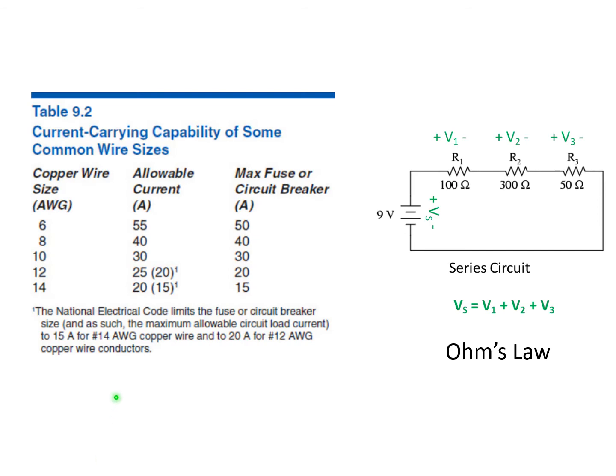And taking a look at current carrying capacity of different size wire. Wire is, at least in the U.S., specified by AWG, or American Wire Gauge sizes. And in a gauging system like this, the smaller the number, the larger the wire. So what we end up with is, say at 14 gauge, 14 AWG, has an allowable current of 20 amps, but the breaker, according to the National Electrical Code, needs to be set at 15 amps. So that way the breaker will trip before you get into an unsafe area with the wire.